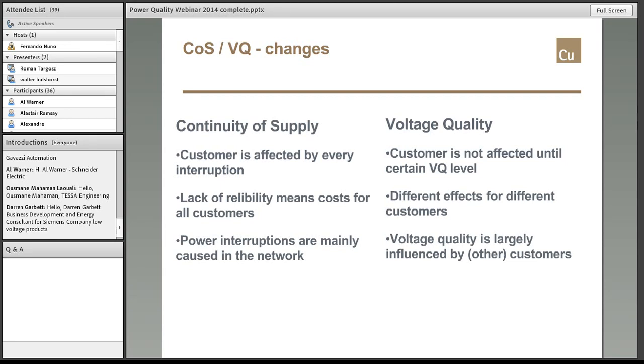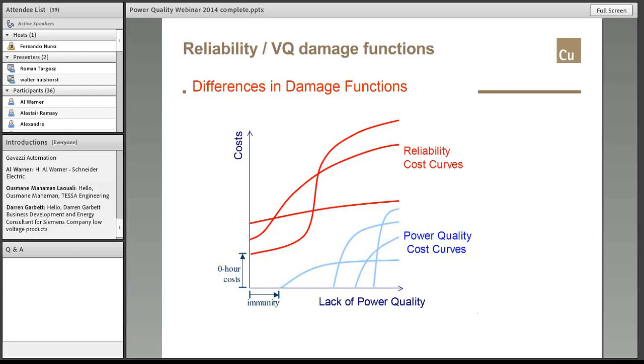Now we've got a chart illustrating what I described on the previous slide. For reliability cost curves for interruptions, we've got, let's say, a zero-hour cost - once the interruption started, we've already got a certain level of cost, and then different shapes of cost curves follow. For power quality, we've got immunity, then costs start to rise, and usually the shape is similar to that of reliability, as usually the product of a voltage quality problem is an outage.